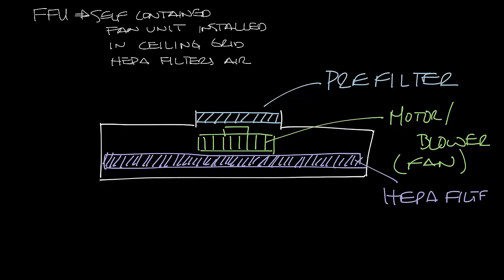Okay, so in this case this is open to the plenum. Air will be pulled in from the plenum through the pre-filter by the motor blower assembly through the HEPA filter and out the diffuser face into the space.